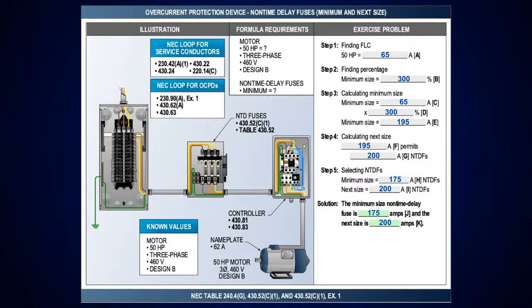Now, the next thing you're going to get into, and I said make sure you do this last week, is right there at table 430.248 and 250, write down sizing OCPD, and then put 430.52(C)(1), and then table 430.52(C)(1). That's where we want to go, because 430.52(C)(1) says, in accordance with table 430.52(C)(1), a protective device that has a rating or setting, listen one more time, not exceeding the value calculated. That means I can't exceed it, so I have to drop down to the next standard size. When I go over to my table and come down and pick up my non-time delay fuse for a full-voltage motor, it's going to tell you to take it at 300%.